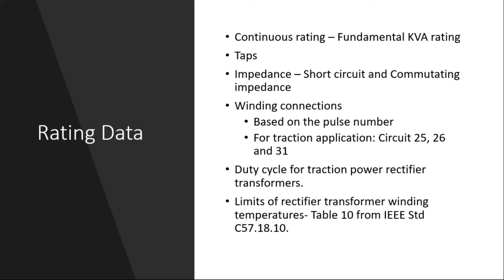The next one is the tapping requirement. These transformers normally have standard tapping requirements on the high voltage side, plus or minus 5%. So there is no complexity in this case. But next is the impedance. So when it comes to impedance, we have a short circuit impedance, which is measured by short circuiting all the low voltage windings.